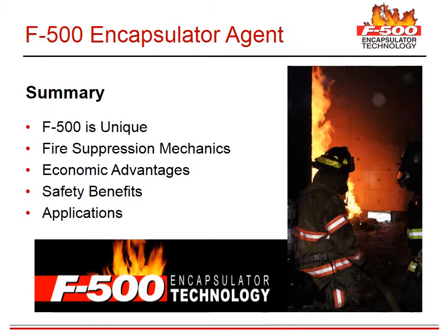To summarize, F500 is not a foam and it is not a wetting agent. It is an encapsulator agent. We discussed how F500 eliminates 3 legs of the fire tetrahedron during the application. F500 is economically beneficial because one agent can handle Class A and Class B fires as well as mitigate spills. Also, less F500 is needed because it extinguishes the fire so quickly.